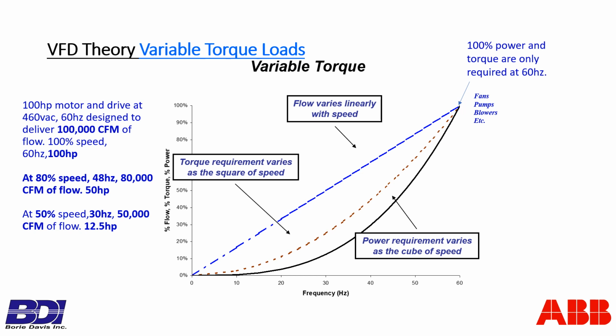Here is the graph of what we've been talking about for the variable torque loads, our centrifugal fans, centrifugal pumps. Again, just like in the constant torque load, we're graphing the frequency along the horizontal axis and the percent flow or speed, the percent torque, and the percent power along the vertical axis. And what we see is this blue curve is the curve of flow. And we said flow is linear with speed, meaning at 60 hertz, we're producing 100% flow. At 30 hertz, we'll produce 50% flow. So we were 100,000 CFM design at 100% speed at 460 volts, 60 hertz, and will require 100 horsepower there. So there's where full power is required. That's why that's there, because this is the power requirement, this curve.